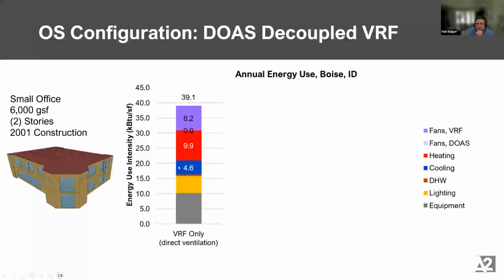Okay, so in our building here, what that results in is a little bit of cooling, right? We have a little heat in that little summer window, a lot of heating, 9.9 EUI, this is kBtus per square foot, and then a lot of fan energy, 8.2 EUI for the VRF fans. And again, driven by the need to always have them running in some way.